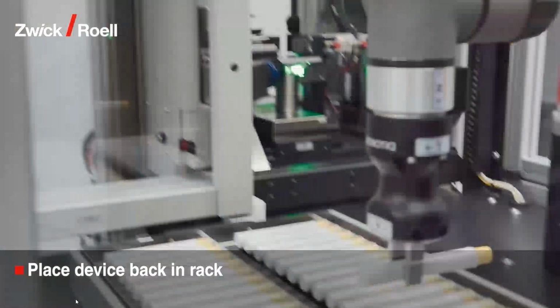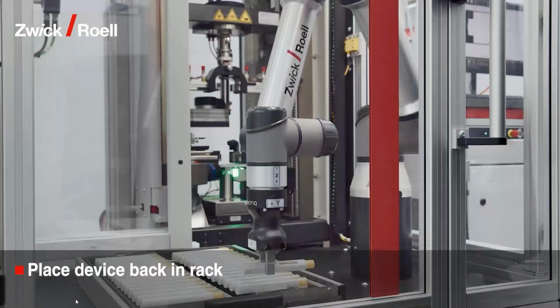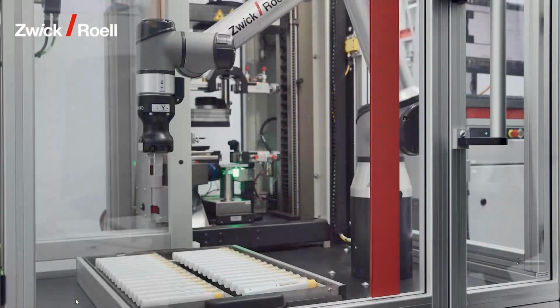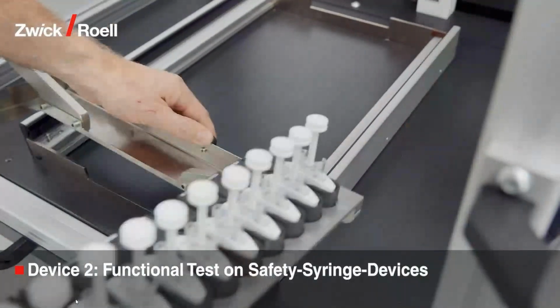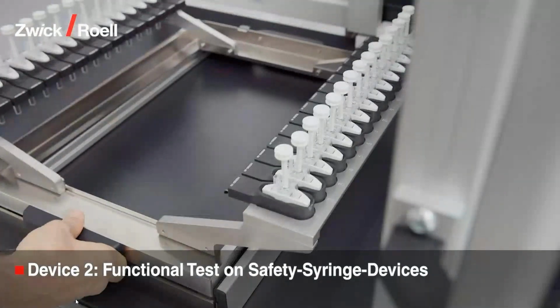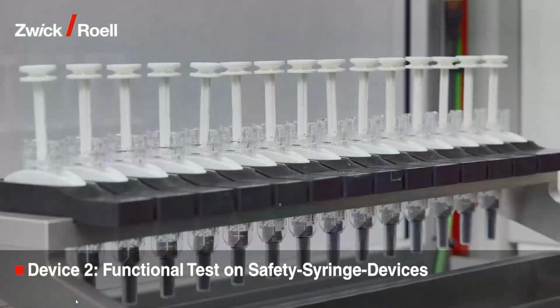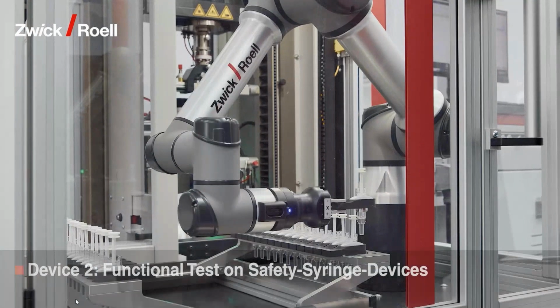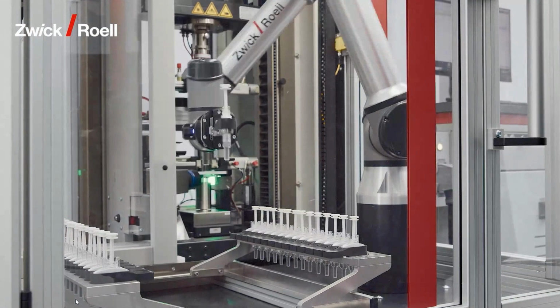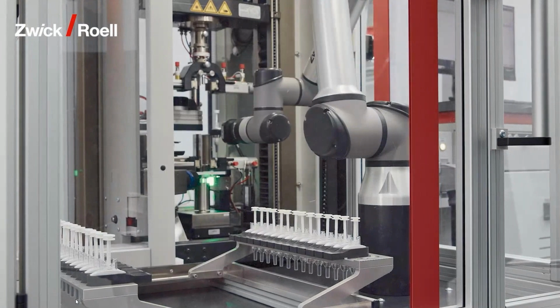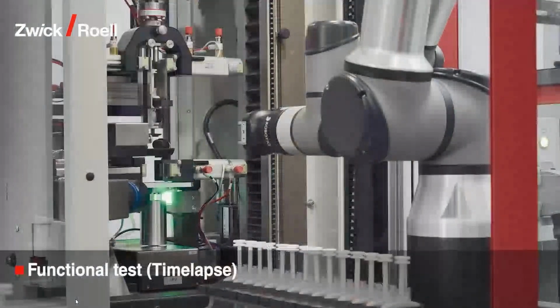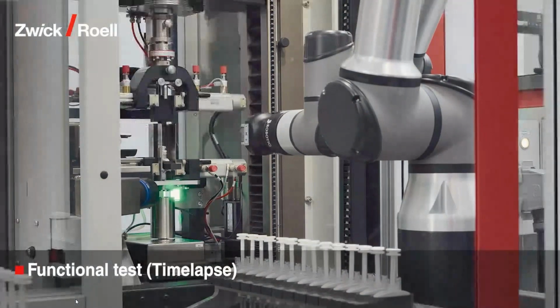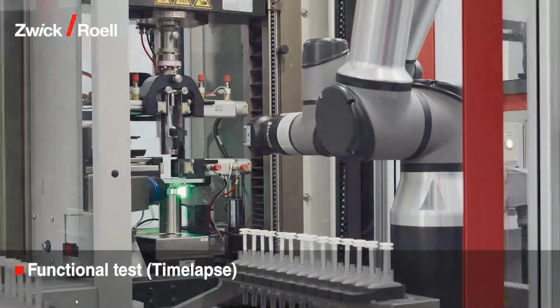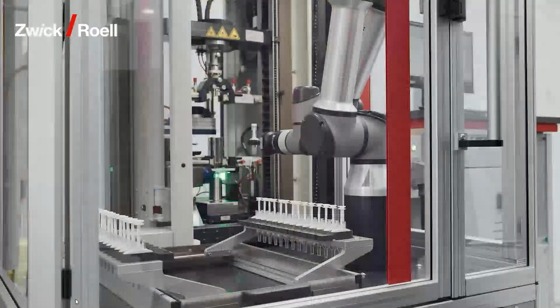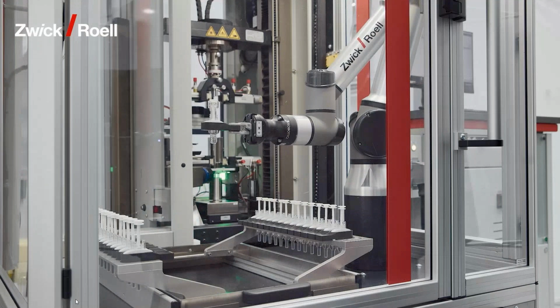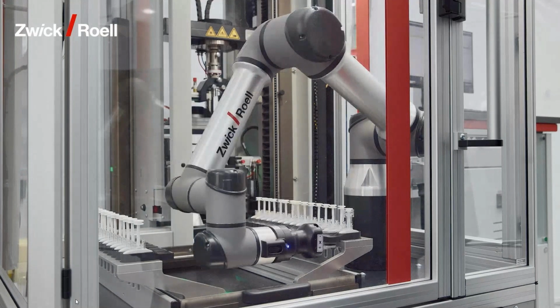With the same robot, we are also able to test the other device, which is the safety syringe device, SSD, or needle safety device, however you want to call it. So here we also have the robot arm using those carriers to bring in the needle safety device. Here again, the functional test in time lapse. And then we're going to place it back at the same position in the tray.